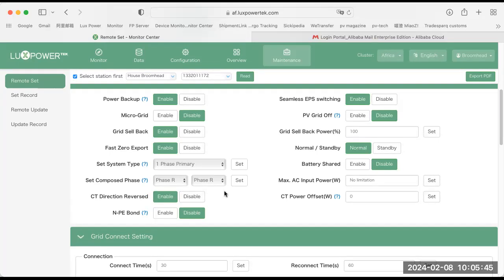and using this button here, you can reverse the direction of the CT. So that basically just tells our processor that the signal coming from the CT must be reversed. It's kind of a handy feature which saves numerous trips back to the site. Correct. Yeah. And you'll know it when the site goes live and it's busy charging the battery, but it shows that it's exporting, simply have a look at the arrow. If it's the wrong way around and it's too much of a fuss to get the clamp off the cable, simply go here and switch the CT.